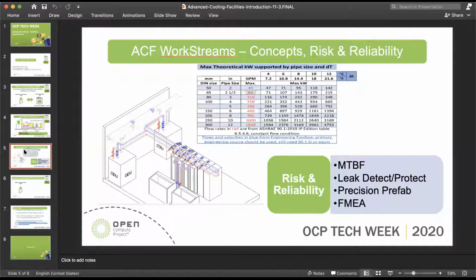What you're also seeing in the picture is the concept of immersion cooling coexisting next to racks, and those racks could be rear door heat exchangers, or in many cases a rack-based cold plate, or rack-based immersion cooling. You could either have drops directly to each one of those, or you may have a CDU down at the end.